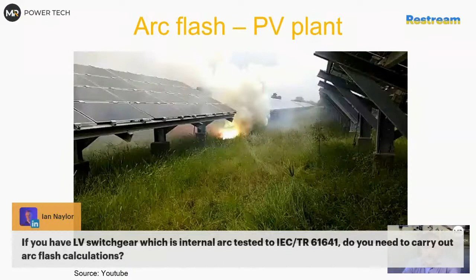I think Mark is referring to the question about ATPV or EBT from the previous. So it is generally the same thing, different tests of course, but ATPV rating or EBT rating is both calories per square centimeter or joules per square centimeter. So 100 calories or 140 calories. I think it was an ATPV test that time, if I remember. It was not tested for EBT.